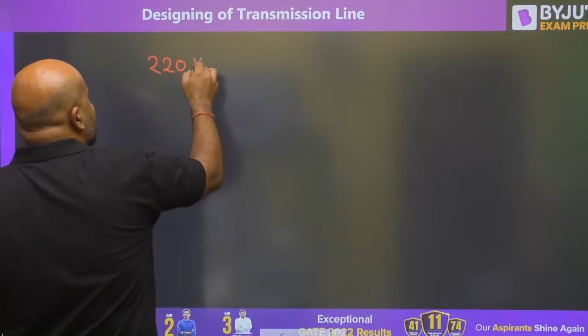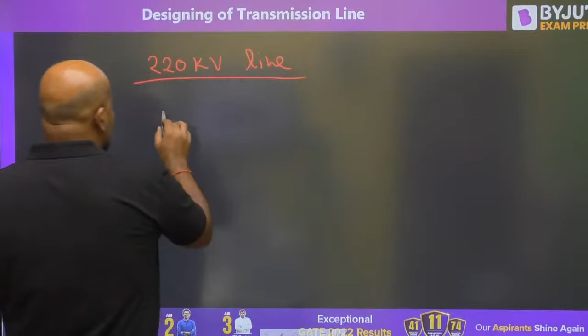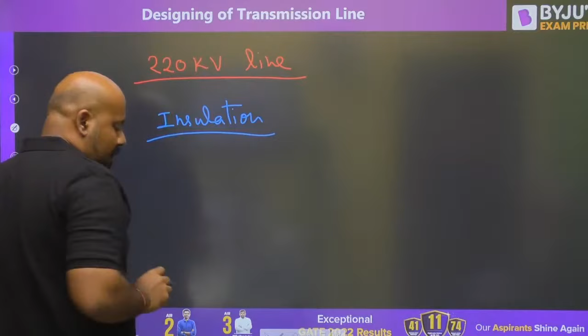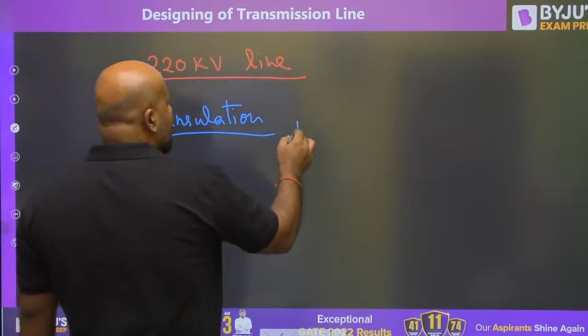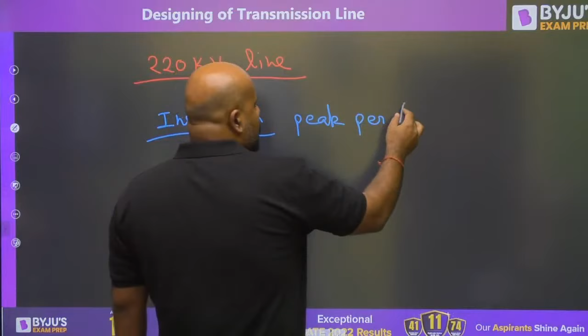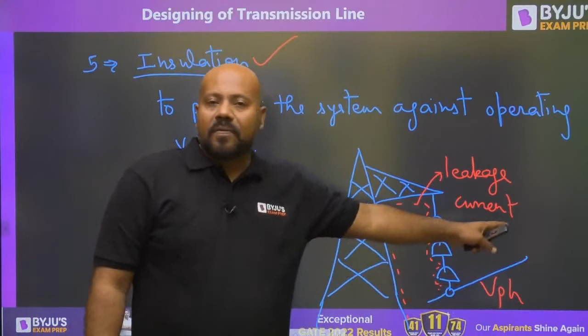Now suppose you have a 220 kilovolt line. What should be the insulation required? Please understand, when you talk about insulation, you are talking about the peak per phase voltage. I say per phase because when you talk about the insulator, you are talking about a single phase conductor only. Why peak value? Because if you can protect your system for the peak value, the rest of the values are automatically protected.